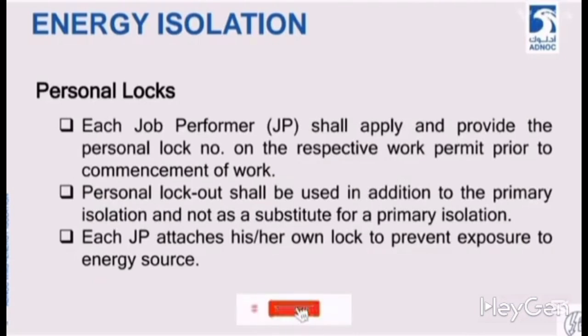Personal lockout shall be used in addition to the primary isolation and not as a substitute for primary isolation. The JP's personal lock will be an additional control to ensure that all involved parties have locked out and tagged out the isolation. We will never consider it a replacement for primary isolation. The permit issuer's PI's or operator's lock is mandatory for this. Each JP attaches his or her own lock to prevent exposure to energy sources. Every JP will mandatorily install their personal lock along with the PI's lock. They will note its number to ensure that no type of energy is accidentally released during the activity, posing a threat to our people.